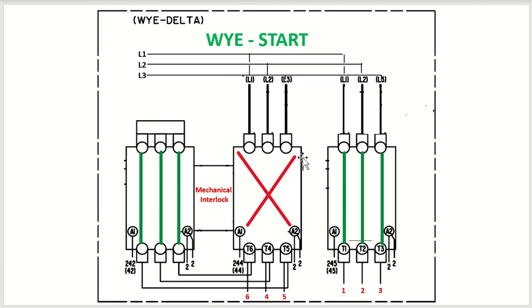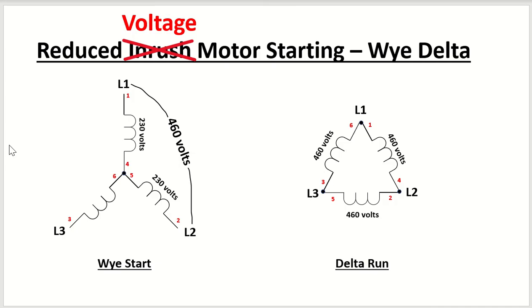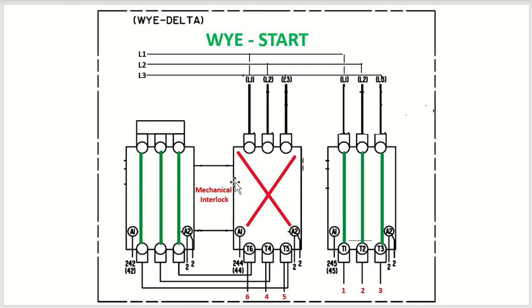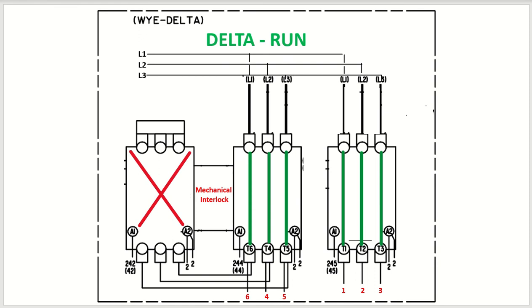When you do the Y start, you put power on terminals 1, 2, and 3, and you do not power 4, 5, and 6, but instead you short 4, 5, and 6 together, and that gives you this common junction here, power on 1, 2, 3, and that's how you start the motor. The power across each winding is half of the full voltage, so it starts and it runs. When you switch it to the delta configuration, you put full voltage on both sets of windings, 1, 2, 3, 4, 5, 6, and you open this shorting contactor.